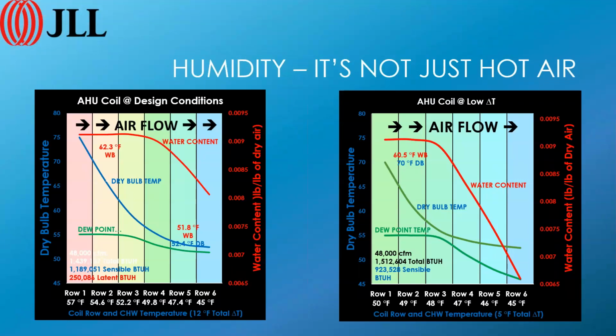So the two outside coils, coil number 5 and 6, you can clean with steam or water, or you can use a foam. But when you start getting into row 3 and 4, you can't really get in there with foam. And if you try to do it with a pressure washer, you just bend the hell out of the fins on the other coil. It's very problematic, and there are instances where I'll look at that coil when it's really badly fouled, and there's only a couple of choices.